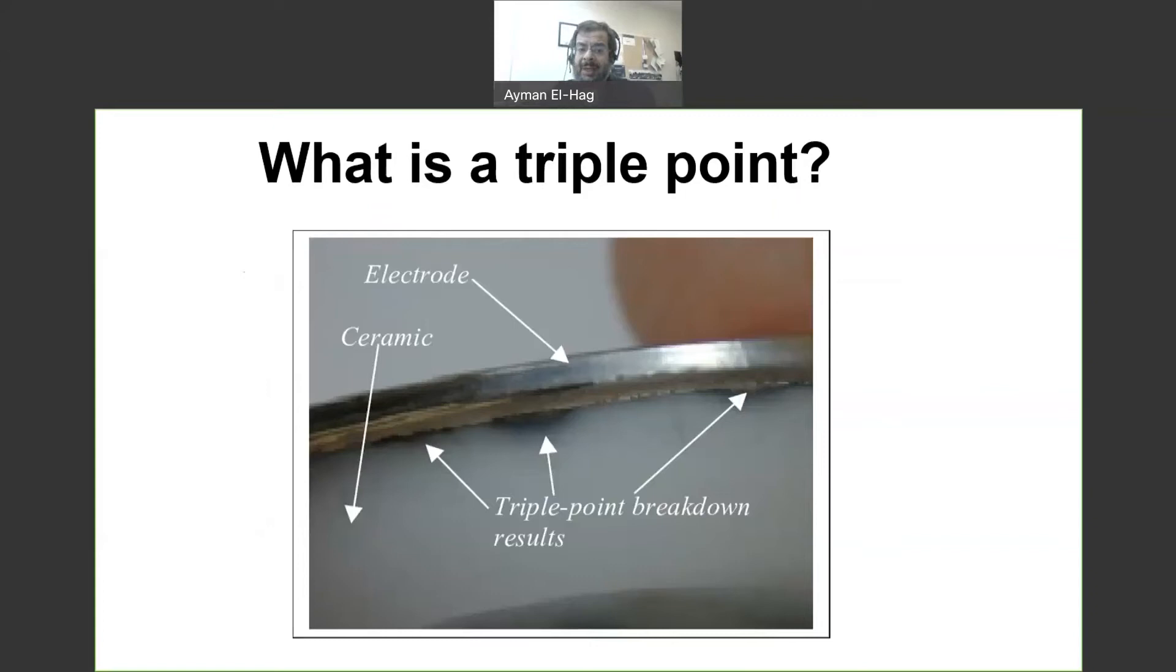So, this is an example where you will have here some breakdown. We have here an electrode. This is a ceramic material, and here is air around it. So, here you can see, this is a triple-point breakdown result. Because of the surface discharge, you can start here signs of tracking start to happen on the surface of the insulator.